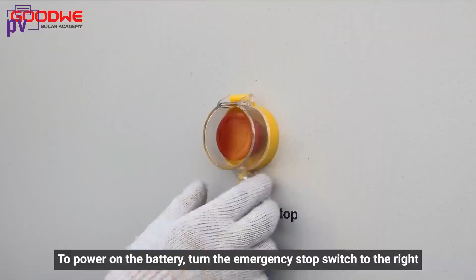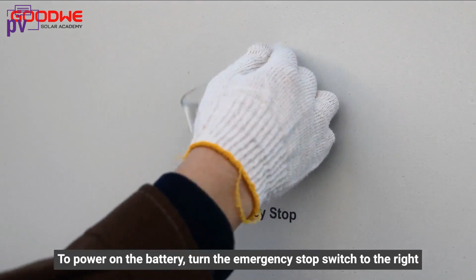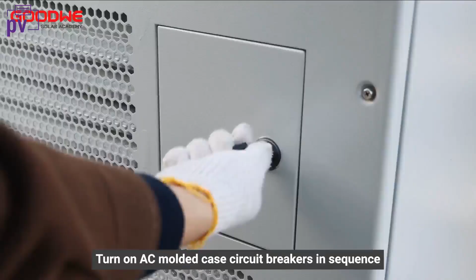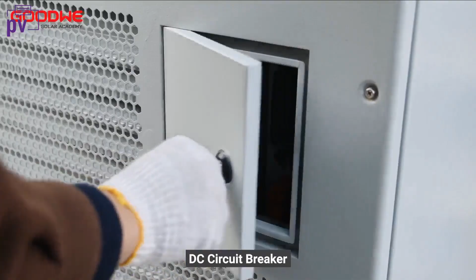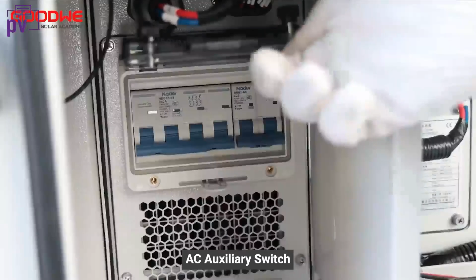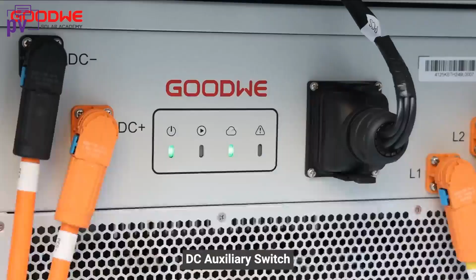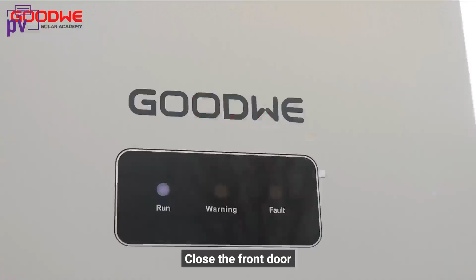Fasten the cover. To power on the battery, turn the emergency stop switch to the right. Turn on the AC molded case circuit breakers in sequence, then the DC circuit breaker, the AC auxiliary switch, and the DC auxiliary switch. The storage converter starts to operate.